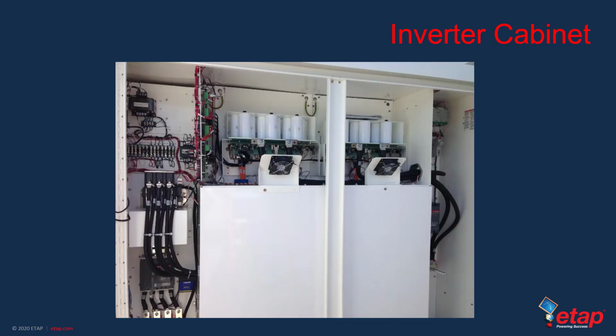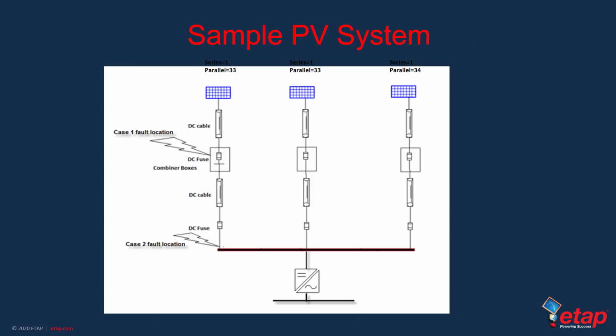The inverter cabinet is shown here in this image, both on the left side, where we have the incoming wires from the combiner boxes, and on the right-hand side, where we have the input to the inverter. In this case, we can do an arc flash analysis on the DC side, on the left-hand side, and we're going to neglect in this particular webinar the calculation on the AC side, which would be the output of the inverter. We'll leave that for a future webinar. Here in this slide, we have a high-level representation or diagram of the photovoltaic system that shows the 2 locations that were faulted: one of the combiner boxes and the actual inverter cabinet, as I showed in the previous images.